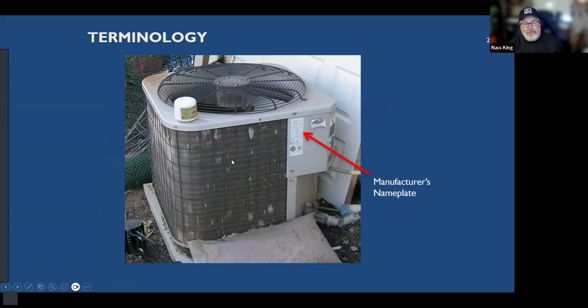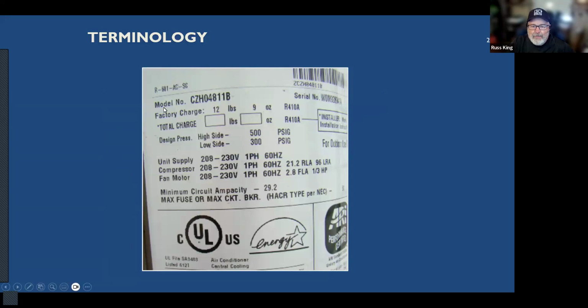So here's a condenser. You go out, look at your condenser outside, and you find something called the manufacturer's nameplate. It's going to be this permanent sticker on the side of it. Okay. And if I zoom in on that, here's what I see. You'll see a model number, you'll see a serial number, you'll see all this Energy Star and UL and all this electrical information and stuff like that. Okay. But look at this model number here, CZH04811B. All right. So if we look at that, somewhere in the middle, we see a 48. That to me means this is a 4-ton air conditioner. All right. The 48 divided by 12 is 4. Okay. And so that's a very good indication that that's a 4-ton air conditioner.